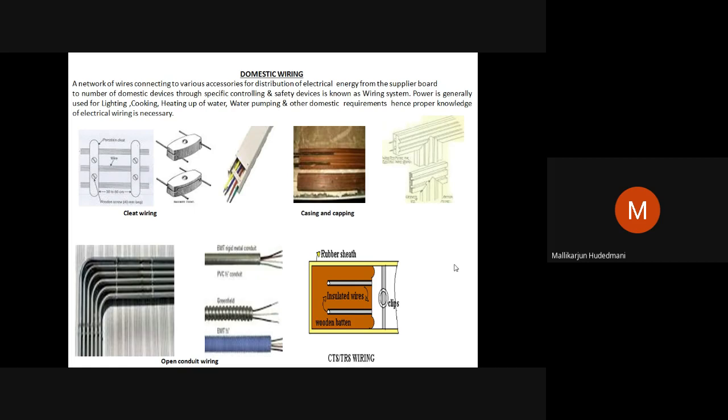But you will find that none of the conductors is visible to you. You will find switchgear to operate and regulate, and the end device at the point of installation. Between those two, there is a cable running inside a conduit like this, which I am showing at the left bottom corner. Conduits run all around the ceiling, in the wall, or on the ground by the shortest way, so that the length of the conductor is saved. In that way, wiring is done by the electrician. That we call concealed conduit wiring.